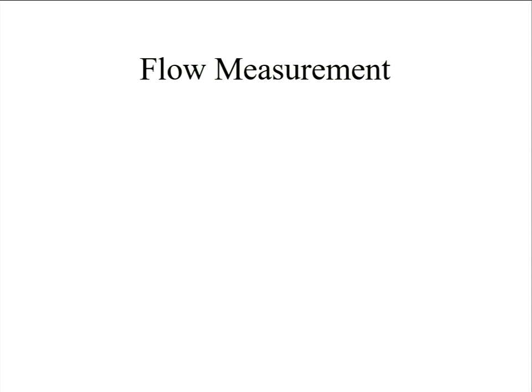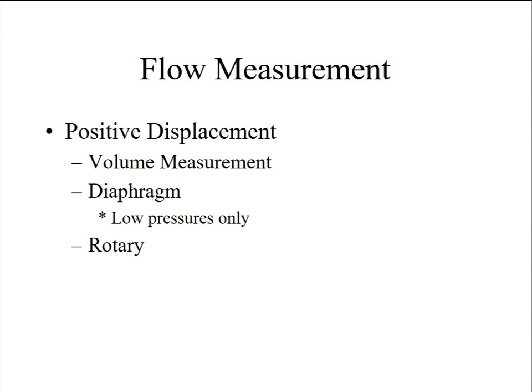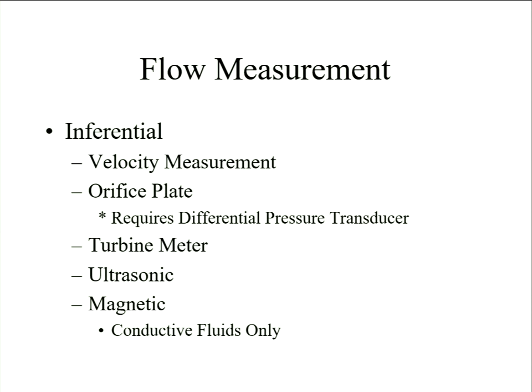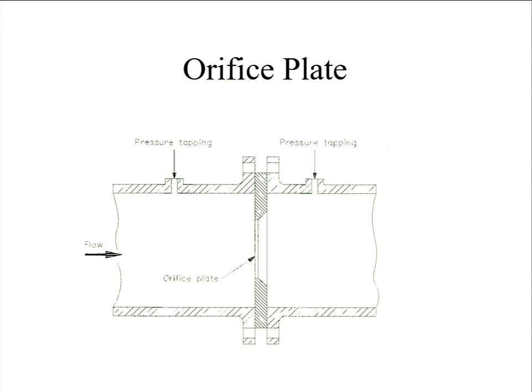But essentially, as the flow comes through this orifice, you create a pressure differential. You measure the differential pressure, and if you're just using it for control or indication purposes, that might be sufficient. If you're using it for fiscal purposes, you need to know things like the density, the temperature, the compressibility. If it's energy, you also need to know the calorific value. You need to put in things like viscosity. You might need to know the altitude you're at, what the gravity is on the day, and so on, when they do the full fiscal examinations. Fortunately, your gravity for your location doesn't tend to change very much. There are some nice standards to read on the orifice plate.